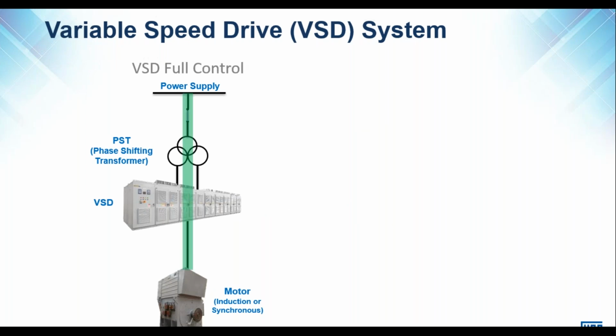Okay, if we are using a VSD for full control, in other words, the VSD is permanently connected to the machine for both starting and operation, then a typical topology would look like this. We have a phase shifting transformer or an integral transformer, the VSD, and a motor. The VSD would need to be sized according to the motor and the load condition, because it is connected permanently into the circuit.